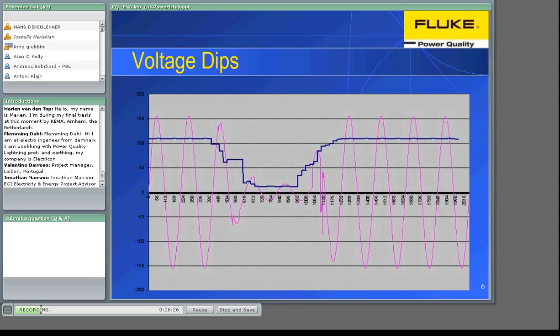When heavy loads, such as large motors, are switched on, the starting current can be many times the normal running current. Since the supply and the cabling of the installation are sized for nominal running current, the high initial current causes a voltage drop in both the supply network and the installation. The magnitude of the effect depends on the network impedance. Interesting is that dips caused by starting currents are characterized by being less deep and much longer than those caused by network faults.